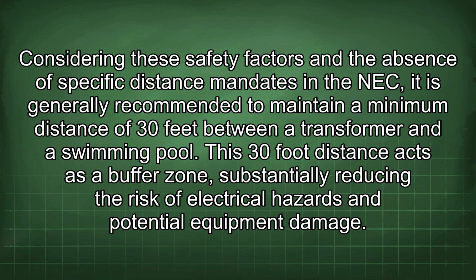Considering these safety factors and the absence of specific distance mandates in the NEC, it is generally recommended to maintain a minimum distance of 30 feet between a transformer and a swimming pool. This 30-foot distance acts as a buffer zone, substantially reducing the risk of electrical hazards and potential equipment damage.